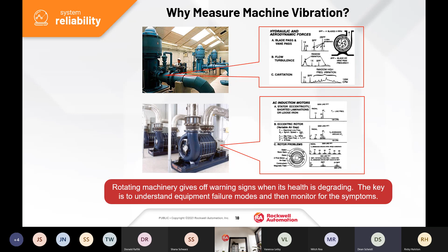In some organizations you might have a reliability office that goes around doing this data collection, and some may be trained in higher level vibration analysis. They might look at these things and determine, oh, we have a bearing going bad. So you're trying to predict failure, being able to shut something down on a scheduled basis versus having it fail without your knowledge, causing much more expense. Every pump and motor in a typical water or wastewater facility may or may not need this type of monitoring, but usually the larger horsepower devices do. Hopefully you've run across this before.